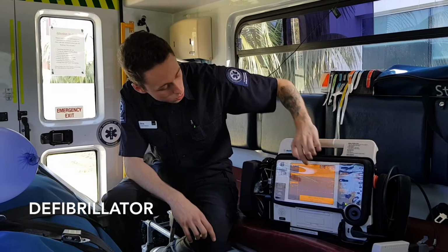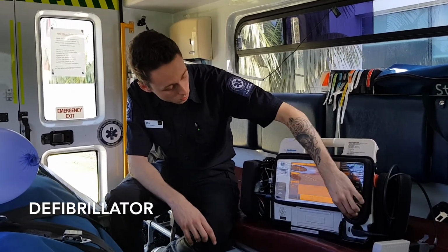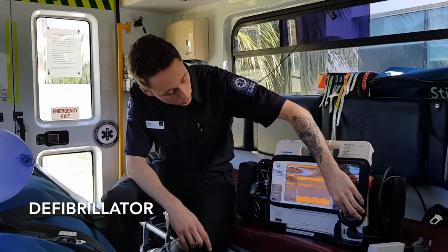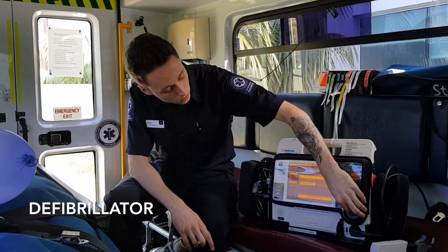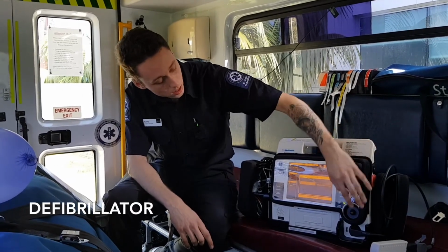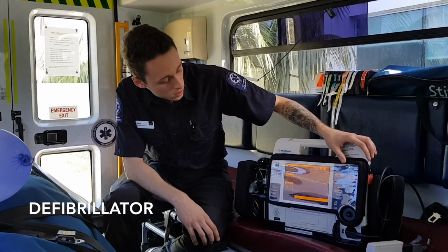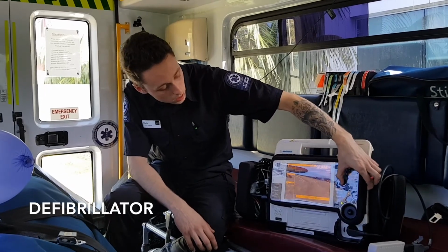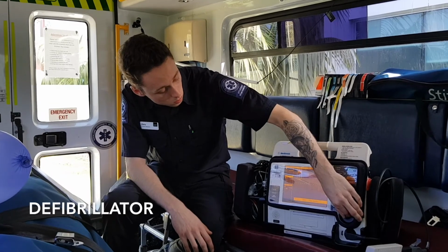If I want to increase the volume of the QRS wave, I will select this here, can increase or decrease the volume that we're after, and then press home screen when done. If I want to increase the size of the QRS wave, I will press the size button here. I will press the desired size we're after.